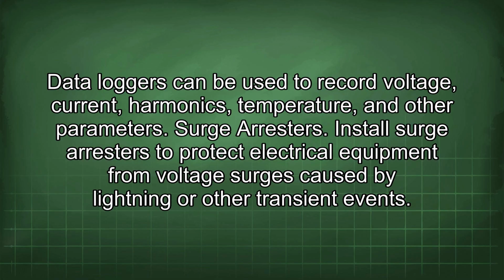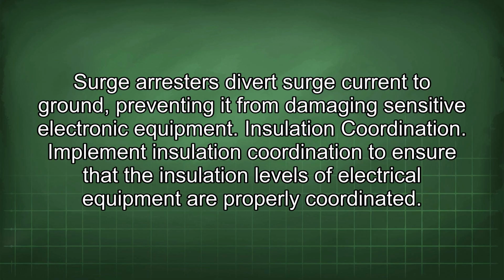Surge arresters. Install surge arresters to protect electrical equipment from voltage surges caused by lightning or other transient events. Surge arresters divert surge current to ground, preventing it from damaging sensitive electronic equipment.